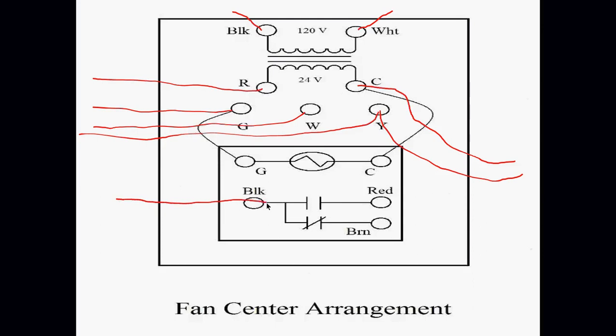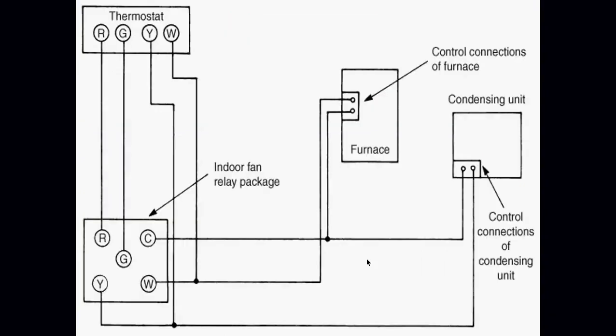My blower motor, I bring line in here. Red goes to my high speed. Brown goes to my low speed, or whatever's controlling my heat side. Could be a fan limit switch or something controlling my heat side. These are really easy to wire. Just because it has a ton of terminals on it, don't let it concern you, because again, they're easy to wire. You just connect the terminals together. That's why they're designed to be so easy to wire. And we're going to look at this in a schematic tomorrow. This just breaks it down a little bit more. My thermostat here connects to the appropriate wires down on my terminals. I wouldn't connect a wire in the middle like I've done here. I'd bring both wires to my W terminal or my Y terminal.